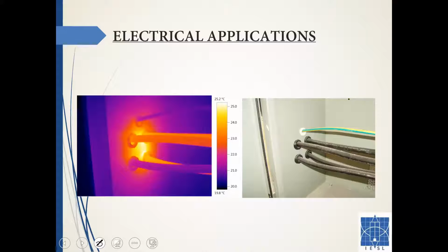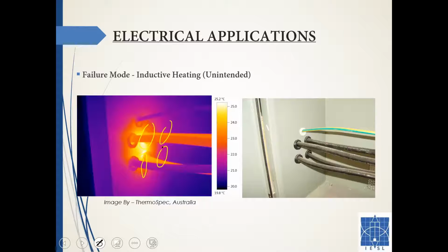Here we call this inductive heating, which is of course unintended. What happens is when you have a three-phase connection, all three phases together, when they enter a certain panel, they each have these individual electromagnetic fields. These electromagnetic fields meet each other right in the middle, and the field strength is high enough for this plate to generate eddy currents.